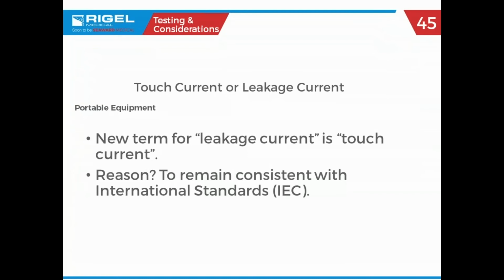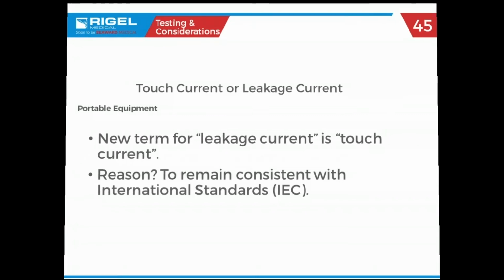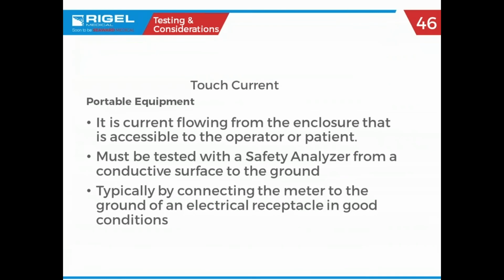Touch current, leakage current. We used to call it chassis leakage. In fact, most of these things will still say chassis leakage on it, because this touch current has been around for a while in the IEC. Was there a question? I'm sorry, did I miss something? No. So chassis leakage is now touch leakage or touch current. Visually, it makes all the more sense in the world, right? You're touching. What's the possibility of a voltage potential there, allowing current to go through your body? So it's a new term for NFPA 99, but it's been used in the IEC standards for quite some time. So this is nothing new.